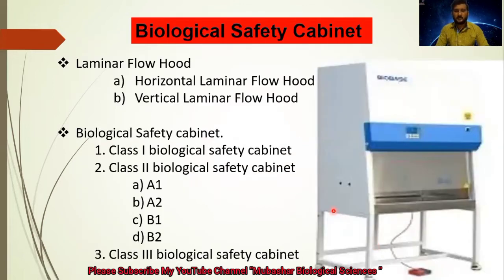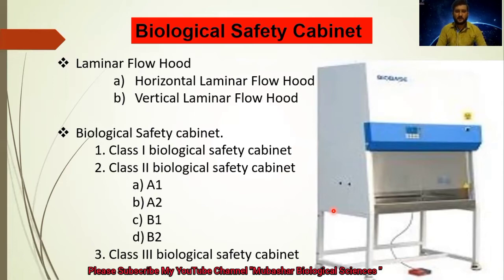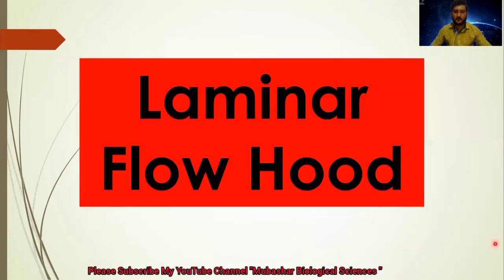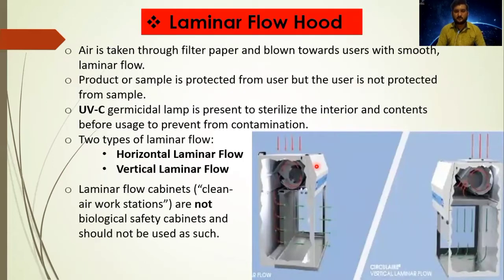The HEPA filter is installed inside the biological safety cabinets or the laminar flow hood, and it decontaminates the particles. In the biological safety cabinet, as discussed earlier, two types are used in the laboratory: first is the laminar flow hood and the second is the biological safety cabinet. Laminar flow hoods have two types — horizontal and vertical — and biological safety cabinets are divided into three classes: class 1, class 2, and class 3. Class 2 is further subdivided into A1, A2, B1, and B2.